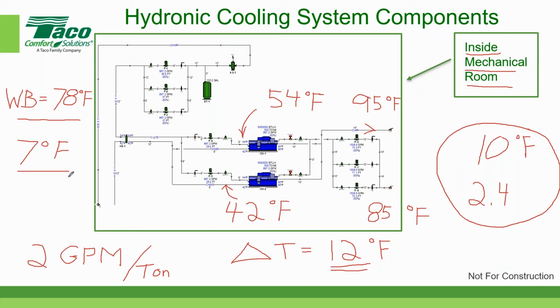So in the heat rejection business, 7 degrees is a reasonable approach for reasonable size cooling towers, without paying a penalty on the size of the tower at one end, and without paying a gigantic penalty on the chilled water side or the condenser water side of the chiller. Apologize for saying that. Any other questions?